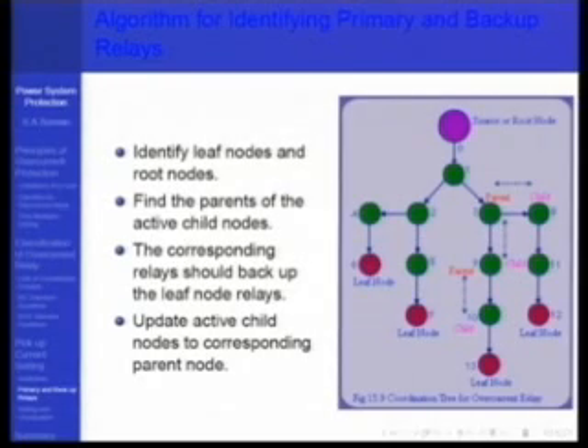There are two issues to be decided in setting. One is pickup current, for which you will do fault studies and find out what the fault currents are for the primary section and for the backup section. Then as I said earlier, your pickup current has to be such that it gives you both primary and backup, and then you will set the pickup current. So that pickup current setting does not require this graph. This graph is only to do the time multiplier, or the TDS or TMS setting.